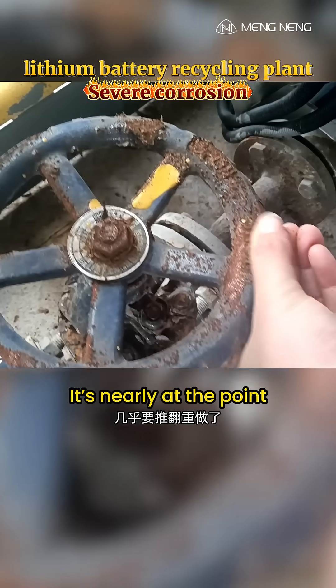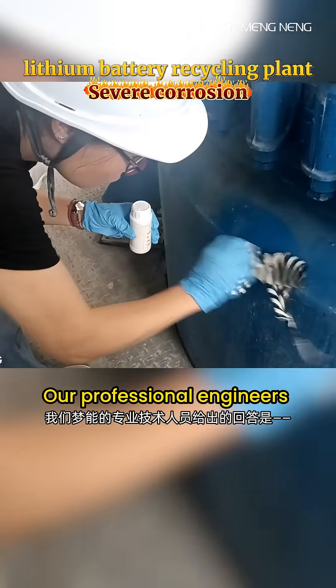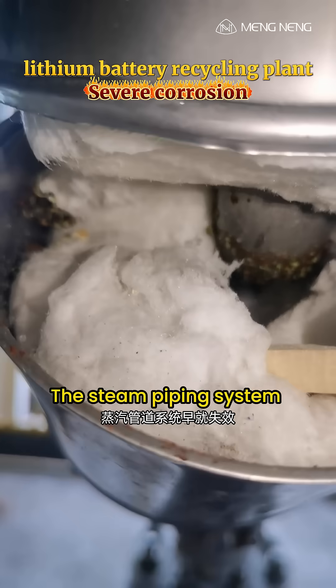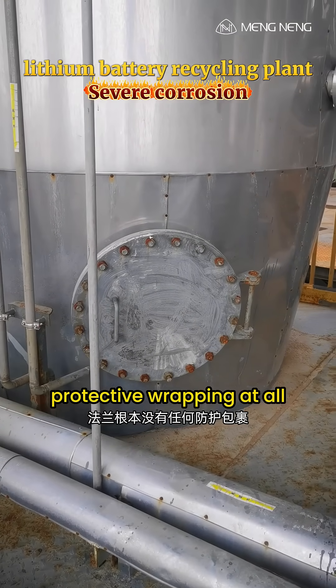How bad is it? It's nearly at the point of needing a full rebuild. The client asked us on site: is there a good coating that can solve this with just one application? Our professional engineers at Meng Neng replied: this isn't something that paint alone can fix. The root cause of the corrosion? The steam piping system had already failed, and the flanges had no protective wrapping at all.